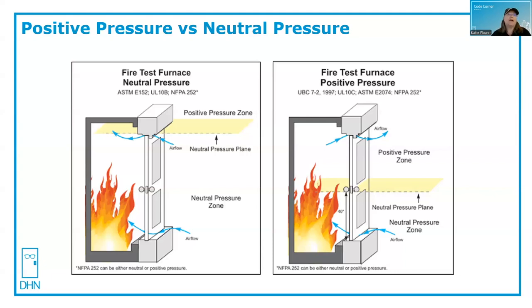So the positive pressure fire door test holds the cool area from underneath the door. But now because the neutral pressure plane is at 40 inches above the sill, any hot smoke, gases, or even potentially flame can be forced out through the top portion of the door. That's why intumescent gasketing is required to pass the positive pressure fire door test for wood doors. Metal doors don't need it because they expand when they heat.